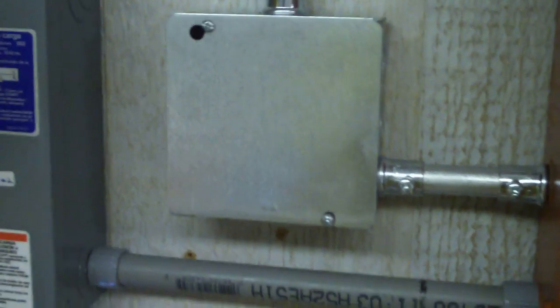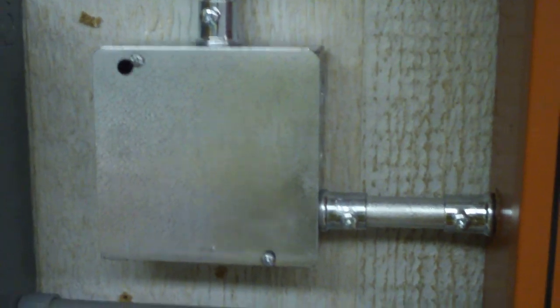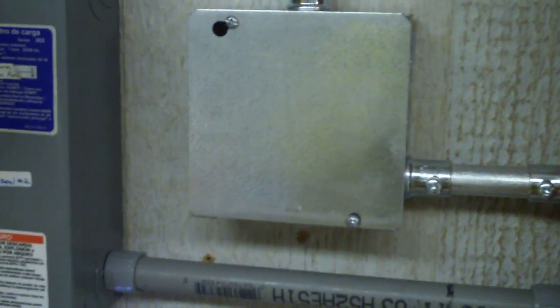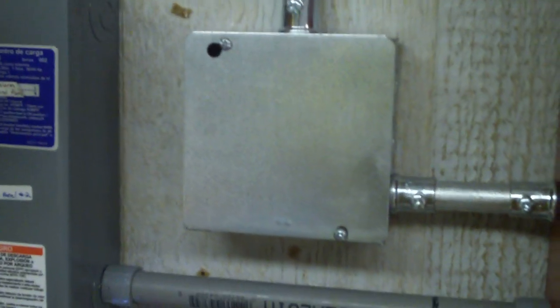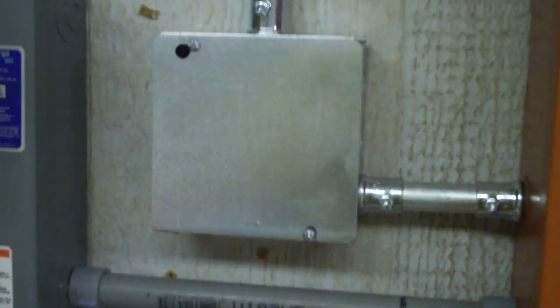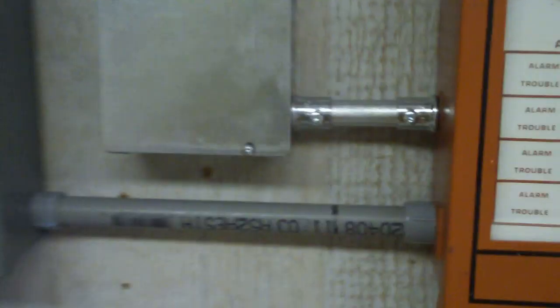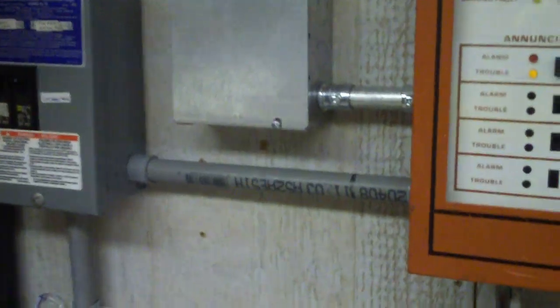I have a brand new back box and cover there as well. This is a 4 and 11/16 inch box. This is what the System Sensor MDL and Wheelock DSM sync module mount to. Other than that it's usually just used as a junction box, and for the box and cover it's about $8. So very expensive box. I don't know why it is.